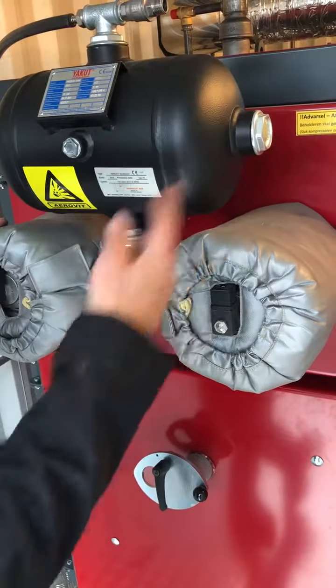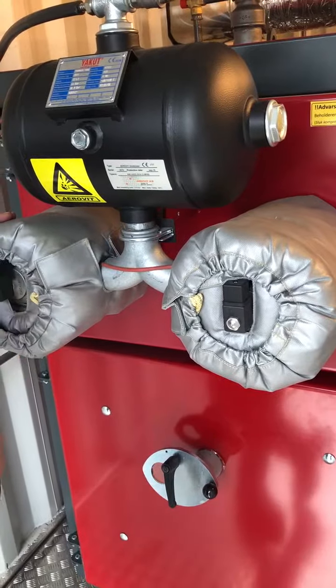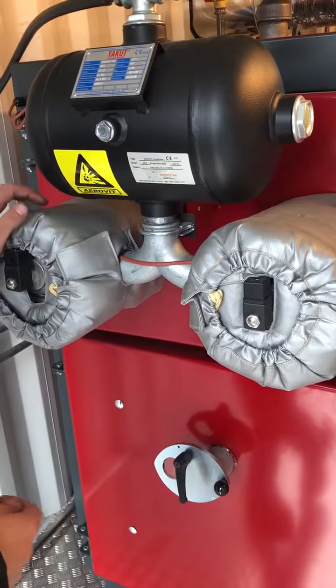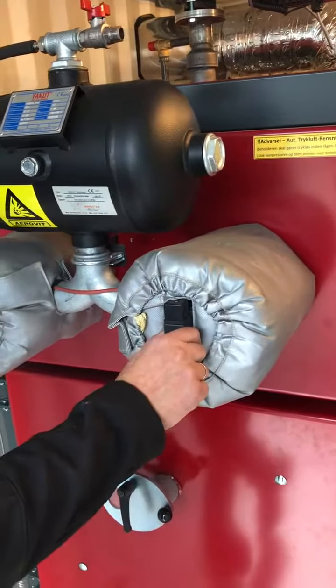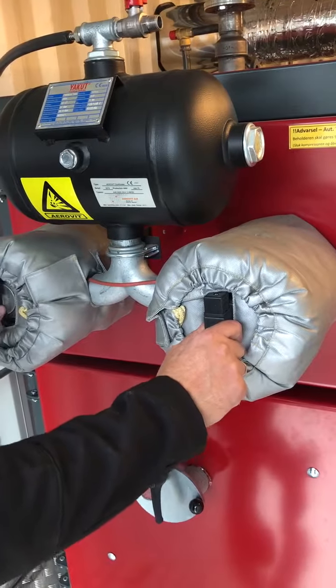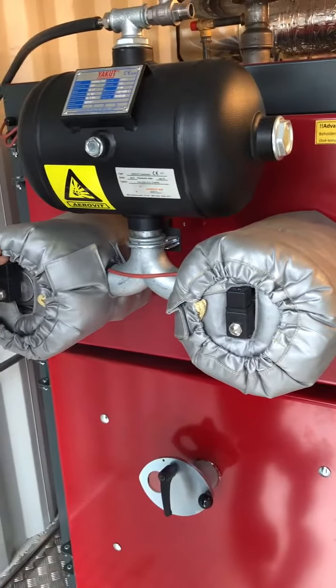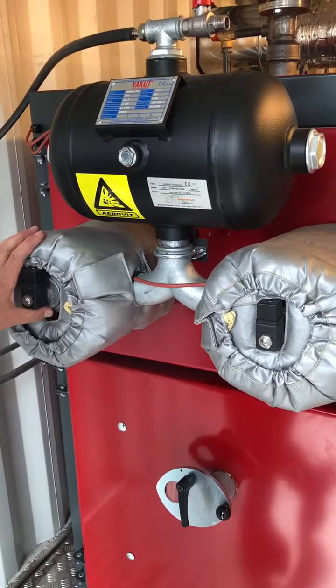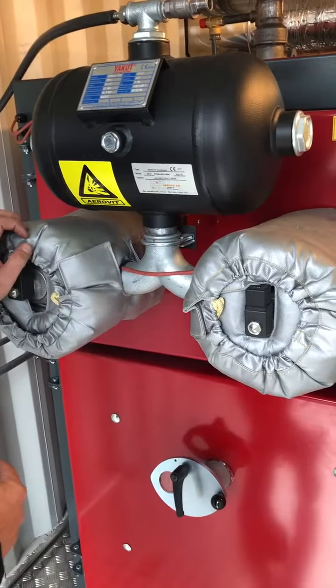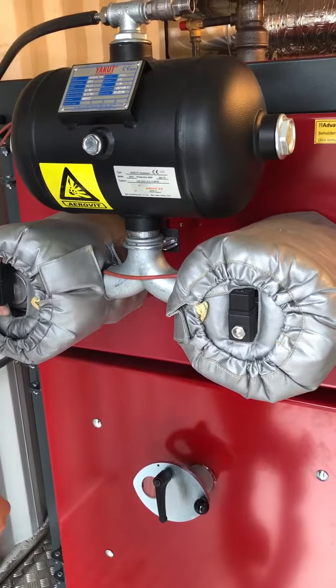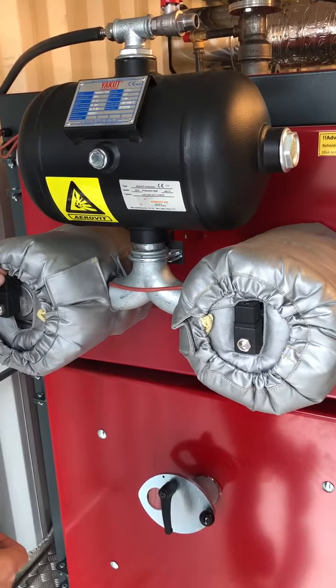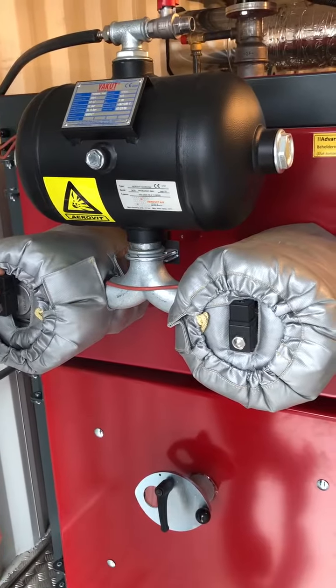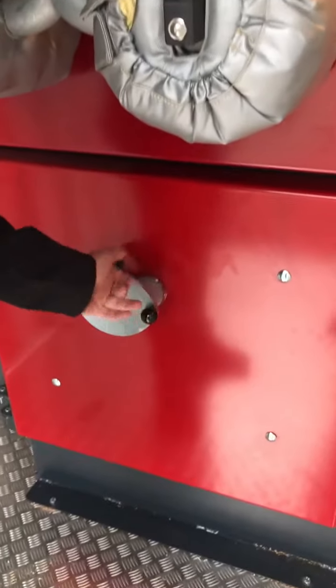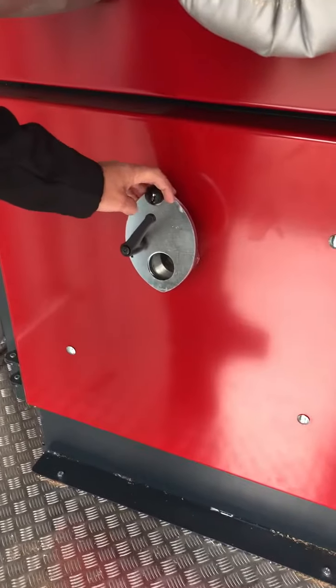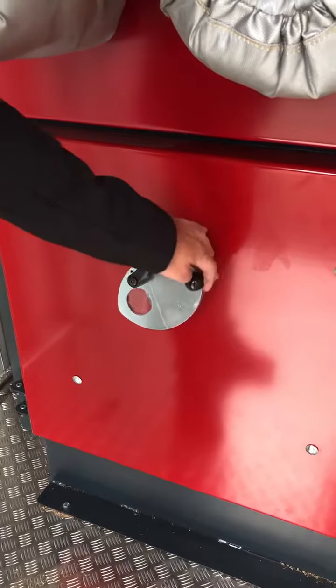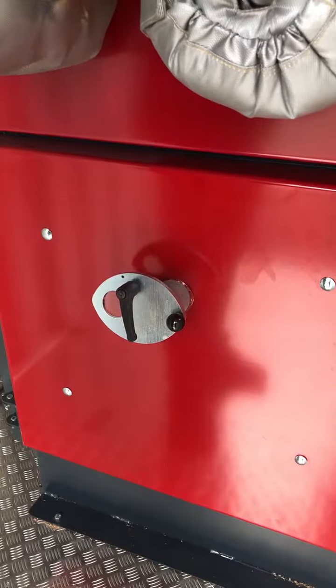And then, by the time set in the computer, the next valve comes on again, perhaps in 3 or 4 or 5 hours. It's better to clean with a low pressure often instead of a high pressure very rarely, because if you have a very high pressure, you can blow a bit of dust out somewhere. We prefer to clean with a pressure of about 4.5 bar on the compressor. If you want to watch into the burner tube and see the flame, remember to shut it off again so it won't get dirt on the glass.